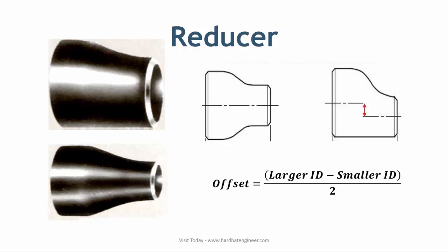Concentric reducers are used in pump and compressor discharge lines. Whereas in eccentric reducers, the center of both ends are on different axes, as shown in the image. This offset is half of the difference between the size of the reducer ends. Eccentric reducers maintain BOP — bottom of pipe — elevation of the pipeline, and are used in pump or compressor suction lines to prevent the accumulation of air pockets.